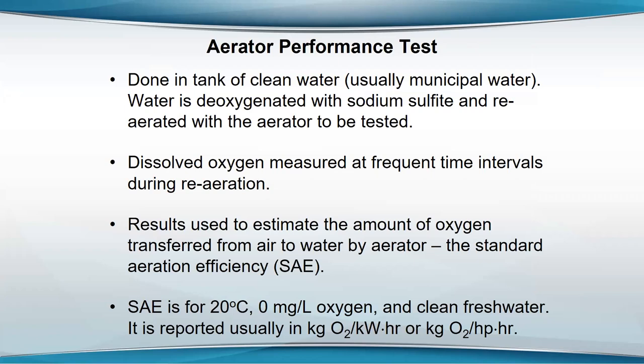There's a mathematical technique for estimating the amount of oxygen the aerator can put into the water. If you divide that oxygen by the power of the aerator, you get the SAE — the standard aeration efficiency — usually reported in kilograms of oxygen per kilowatt hour, or kilograms of oxygen per horsepower hour. The power can be calculated at the aerator shaft or, more commonly, counted as the power going into the motor — the wire power as opposed to the brake power.